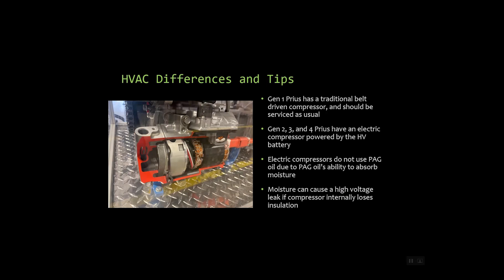And that's due to PAG oil's ability to absorb moisture. If I have moisture in my oil, it can conduct electricity and cause a high voltage leak. So we use ND11 oil for this, and that will not suck the water or humidity out of the air and cause any voltage leaks. If my compressor goes bad, it could leak high voltage to the compressor case if it's not insulated by this oil here.